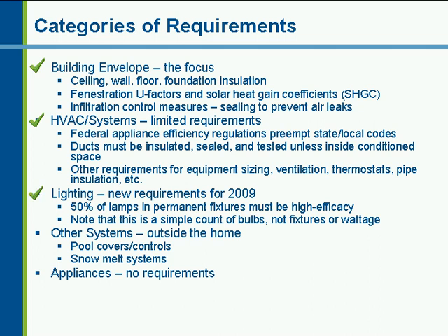Lighting, as I mentioned earlier, is a brand new requirement in 2009. The requirement is fairly simple. We'll talk about it more later, but basically 50% of the lamps in permanent fixtures must be high efficacy. And a high efficacy lamp would be something like a compact fluorescent bulb.